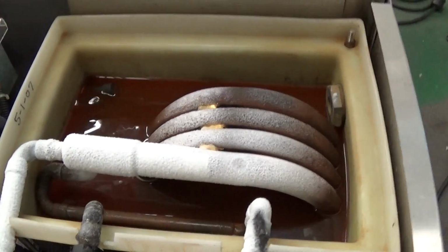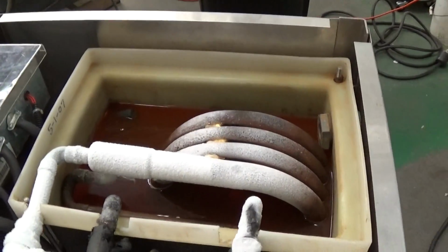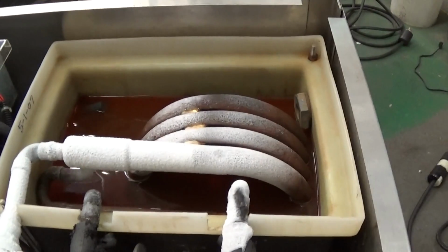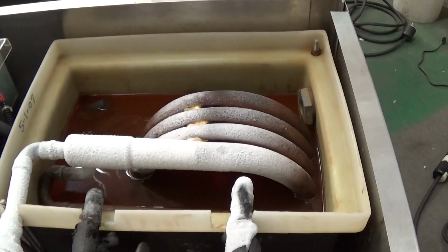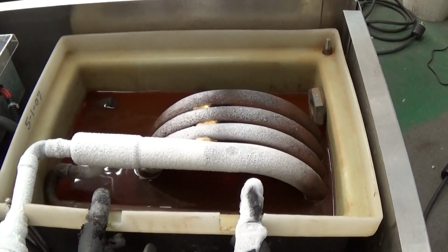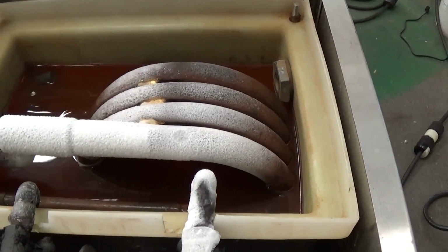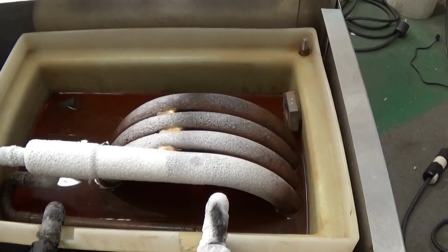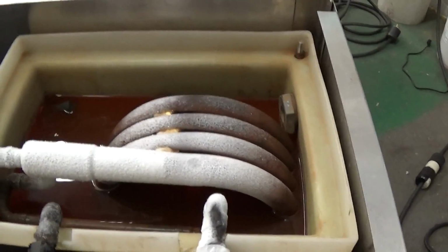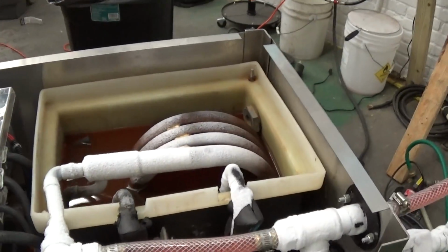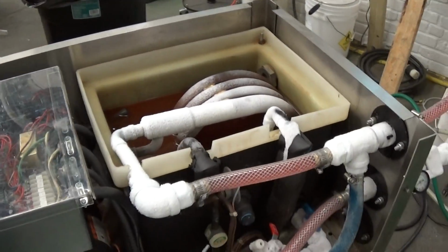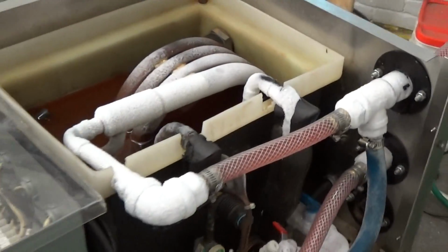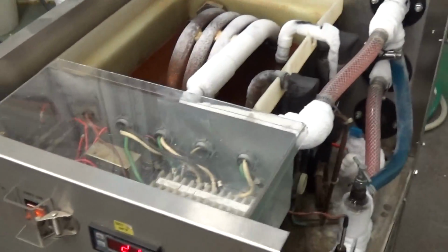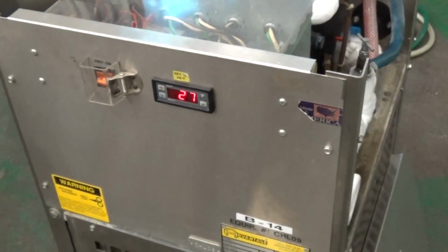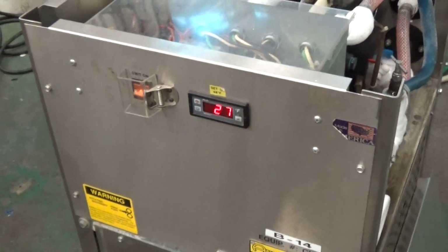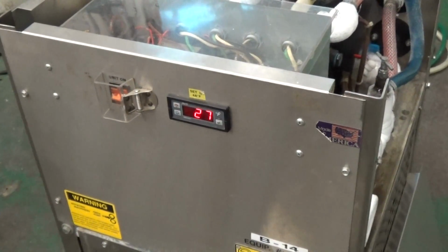Again, we have about a 30% glycol mix here. You should too. Anytime you run a chiller below, say, 48 Fahrenheit, you really need to have some glycol in there, because what's taking place in that exchanger are temperatures below freezing. A lot of people don't realize that, and they get errors and pressure alarms, and they're like, well, I only have it set at 34 Fahrenheit, 36 Fahrenheit, that's not freezing. Well, yeah, it is, because there's temperatures taking place inside that exchanger.